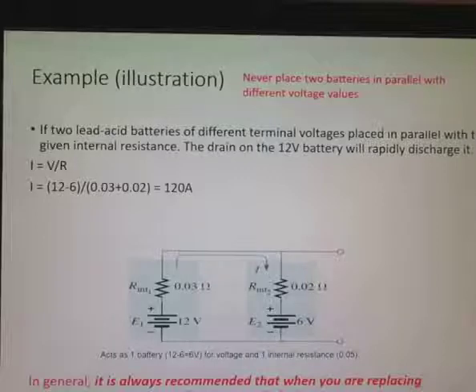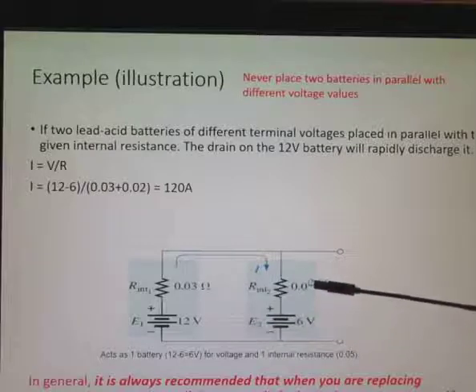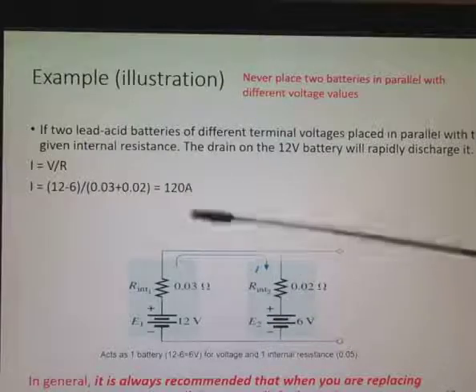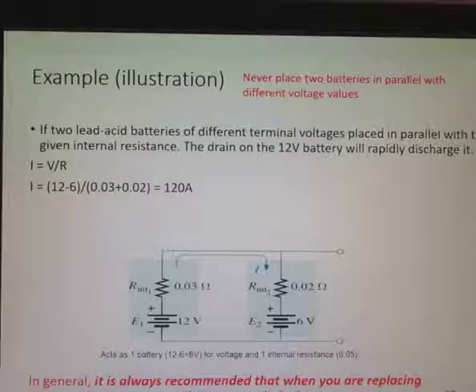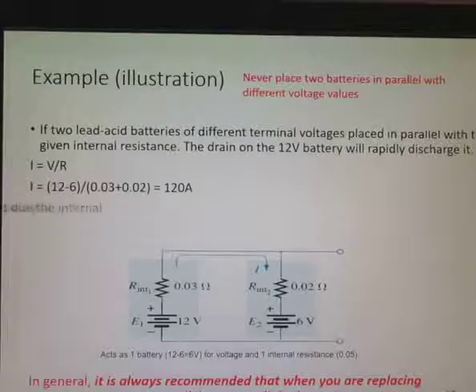And that's the reason why when you change batteries, you want to change them all at one time. So if you have two lead acid batteries of different values, what happens is, using Ohm's law, you get the voltage is 12 minus 6, and the resistance are these two here added, and I get 120 amps. So you get a lot of surge of high current, very dangerous. And it's always recommended that when you replace batteries in series or parallel, replace all the batteries.